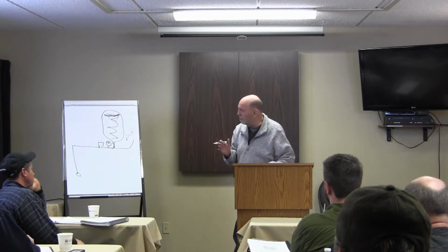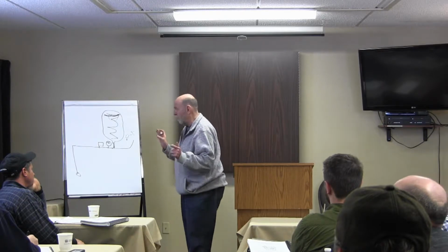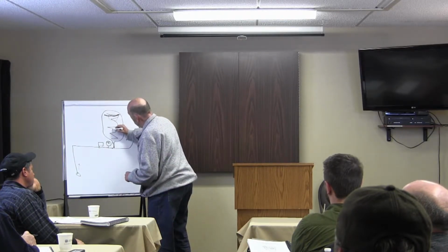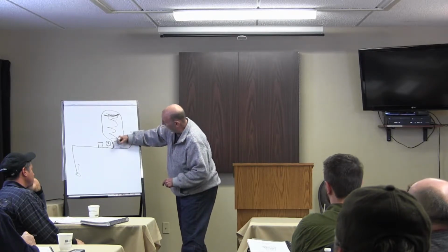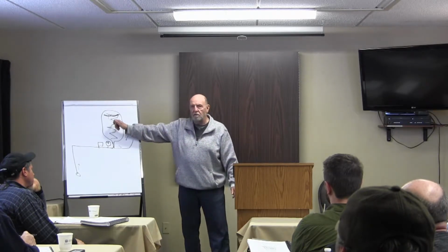Now, there are some balanced systems, and I had it happen to me one day. It only happened once, but it's out there. I talked to the well guy, and he said, yeah, this is rare, but it does happen. This is pushing water out at 4 gallons per minute. It's coming in at 4 gallons per minute, and it's going out at 4 gallons per minute. So they're supplying and taking out at exactly the same rate. So the pressure never changes. That means the switch clicks and never comes back. So when you're running water, you're always running it from the well.